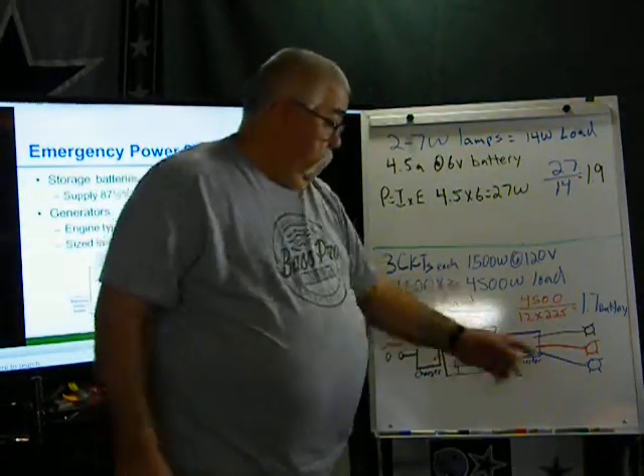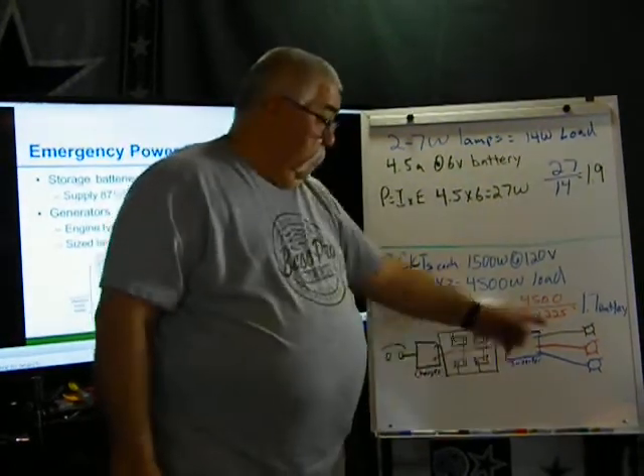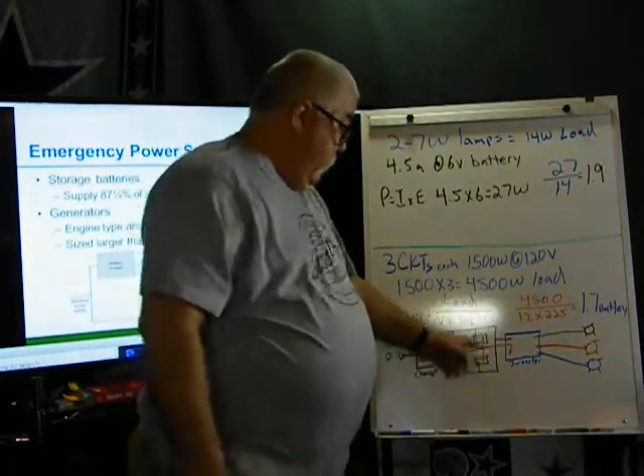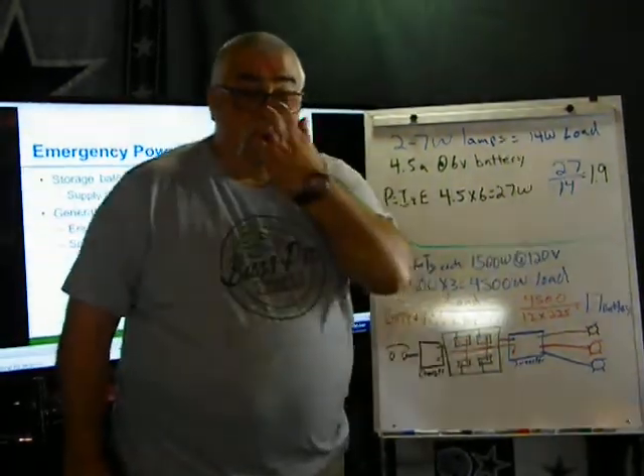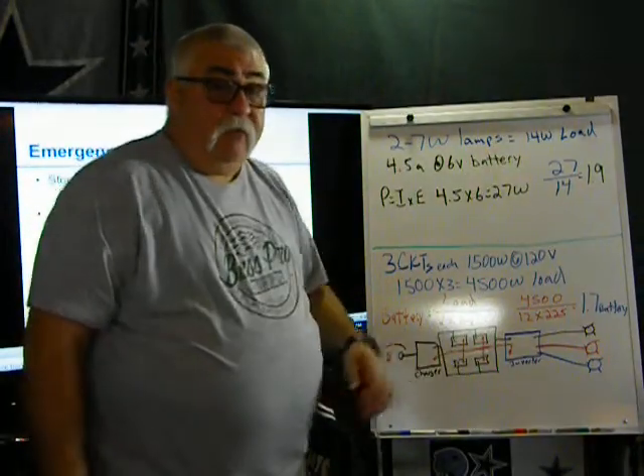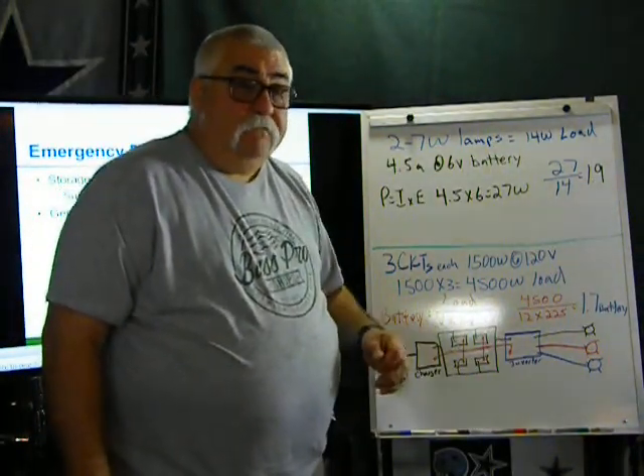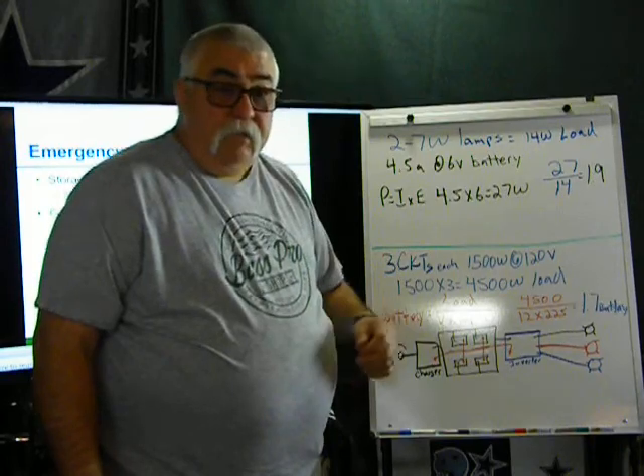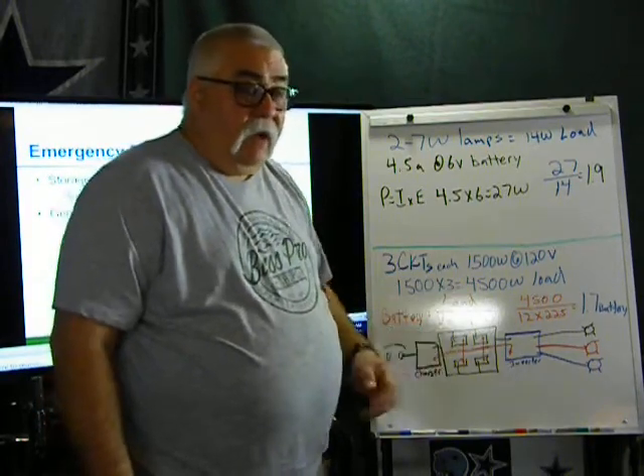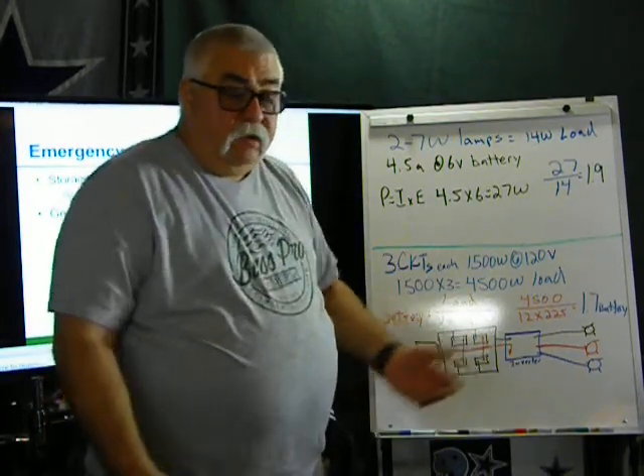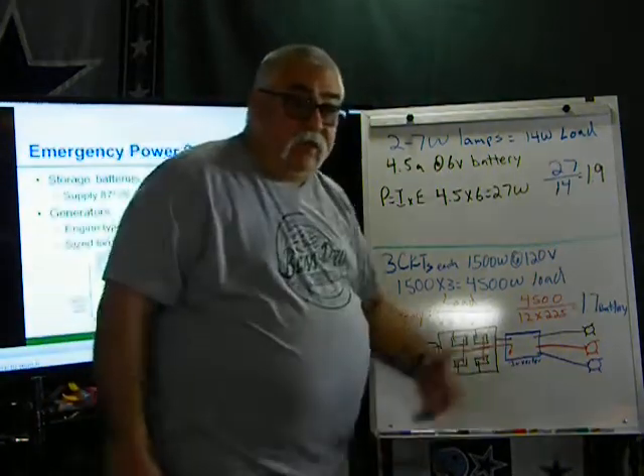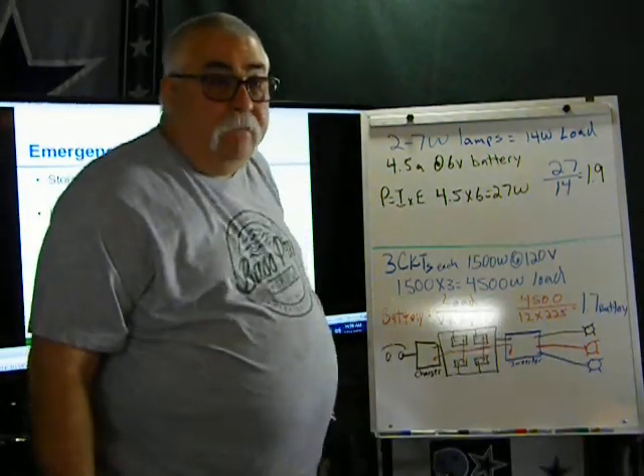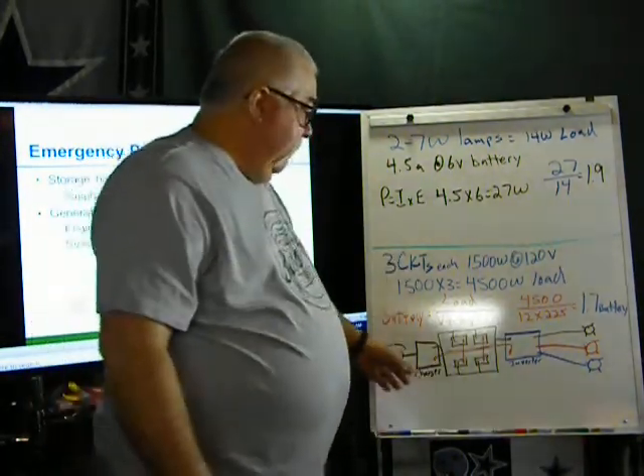I can walk the floors. How many lights went out? If all the lights went out, that means my batteries aren't performing the way they're supposed to. These batteries you have to maintain. You have to clean them. If you're using a lead acid battery, you have to make sure of that; if you're using the gel cell that are sealed, then you don't have to worry about it. If these are lead acids, guess what? You've got to maintain them. You've got to check them to make sure that the levels are proper.